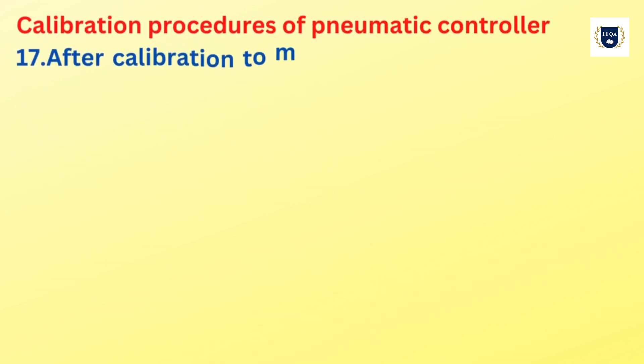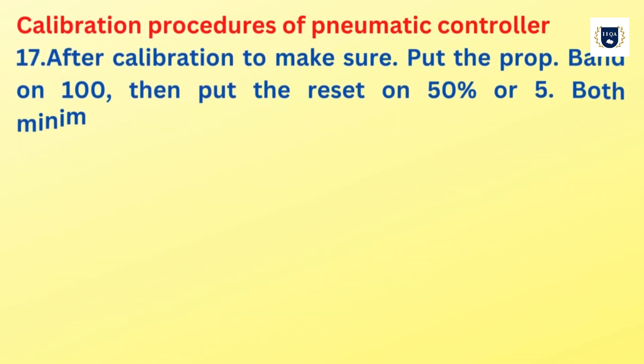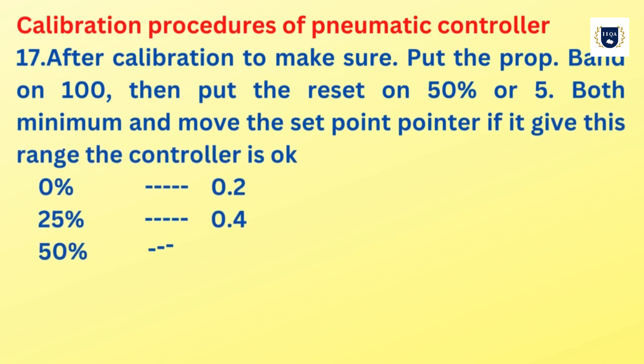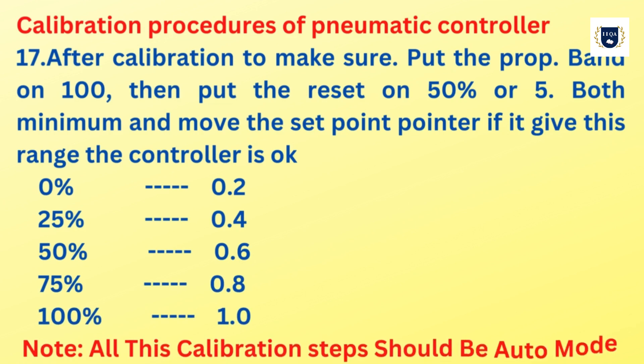After calibration, to make sure: put the proportional band on 100, then put the reset on 50% or 5. Move the set point pointer — if it gives this range, the controller is okay: 0% = 0.2 bar, 25% = 0.4 bar, 50% = 0.6 bar, 75% = 0.8 bar, 100% = 1.0 bar. Note: all calibration steps should be in auto mode.